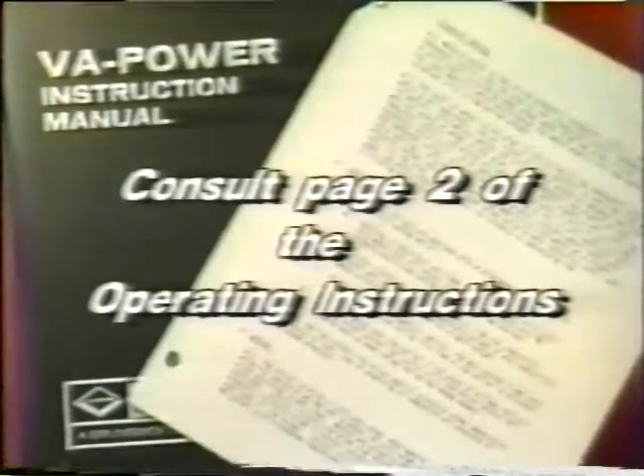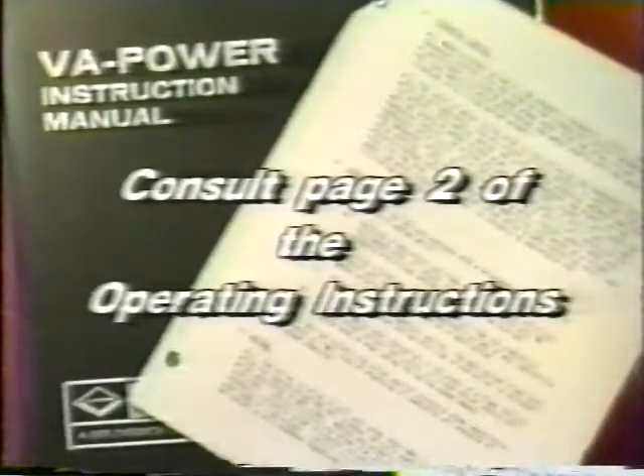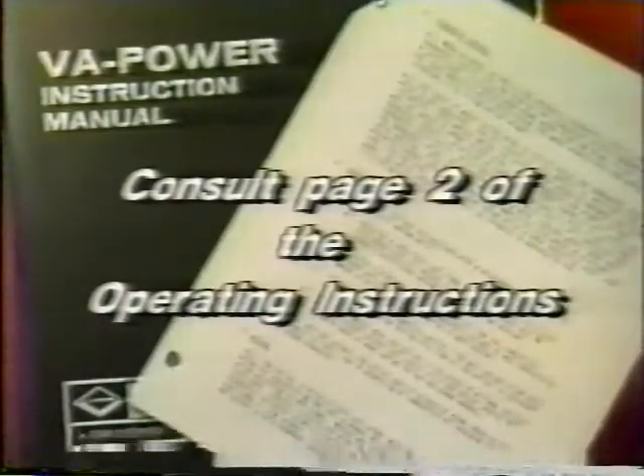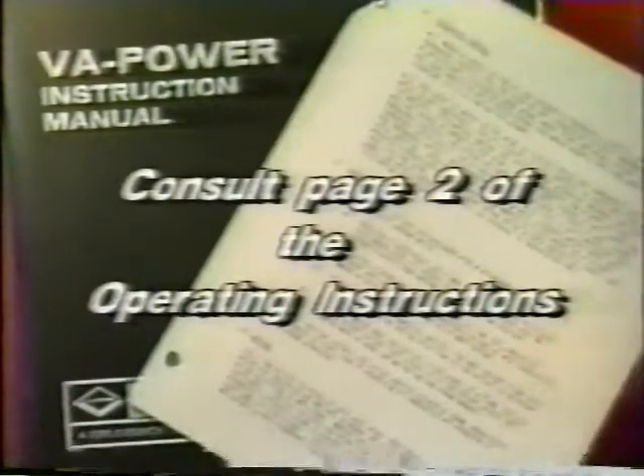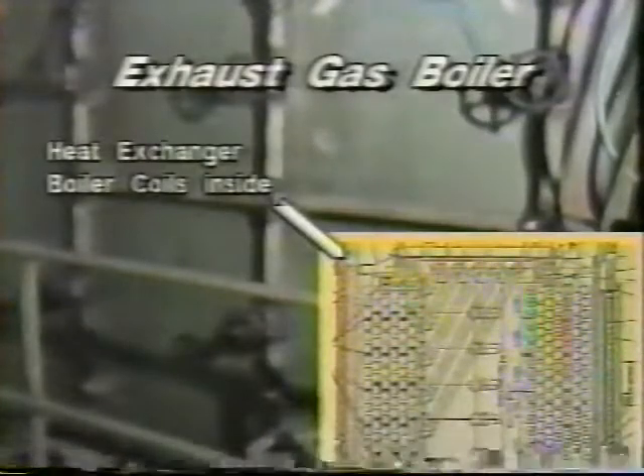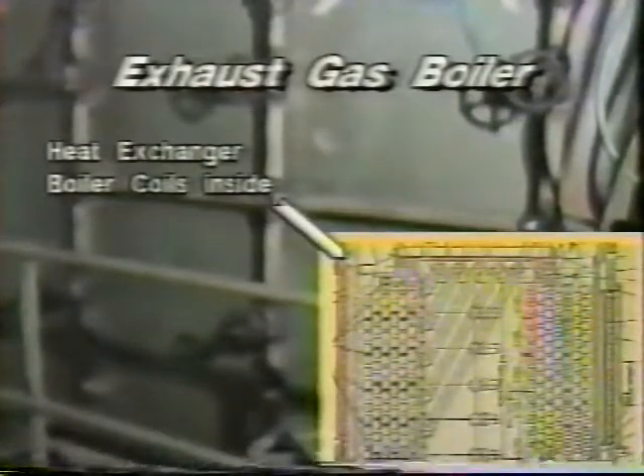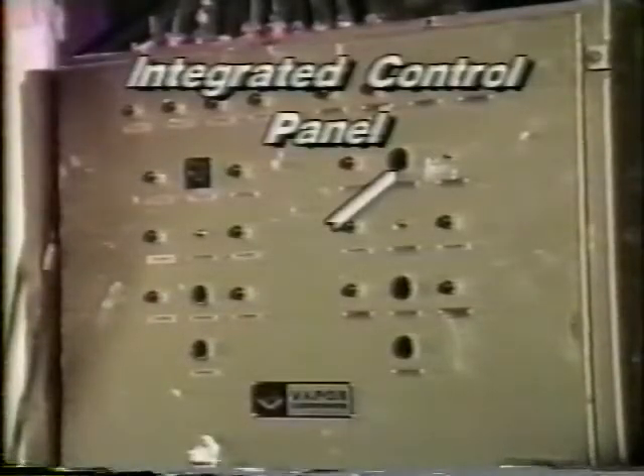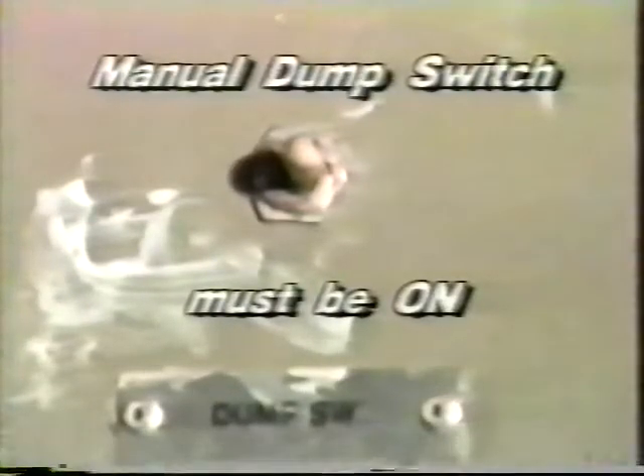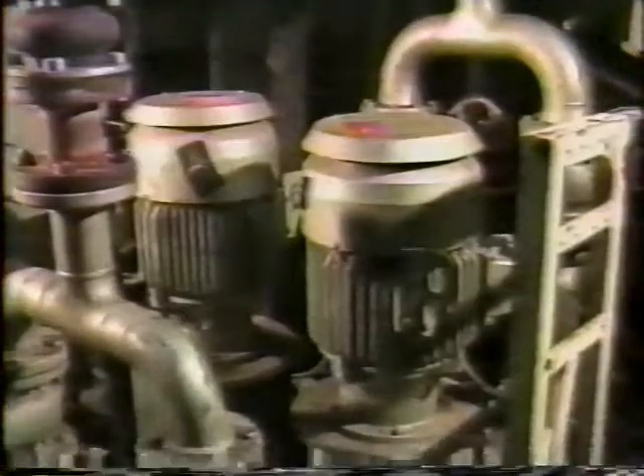Consult page 2 of the operating instruction for the exhaust gas boiler in the VA-Power manual for the operating steps for filling the boiler. Once the boiler coils are filled with water, all the safety resets should be reset. Then the start reset switch on the integrated control system panel is pressed. The manual dump switch shown here must be in the on position. Next, start the flow of cooling water to the recirculating pump.